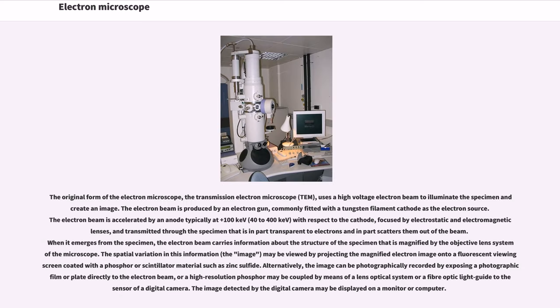The original form of the electron microscope, the transmission electron microscope TEM, uses a high-voltage electron beam to illuminate the specimen and create an image. The electron beam is produced by an electron gun, commonly fitted with a tungsten filament cathode as the electron source.